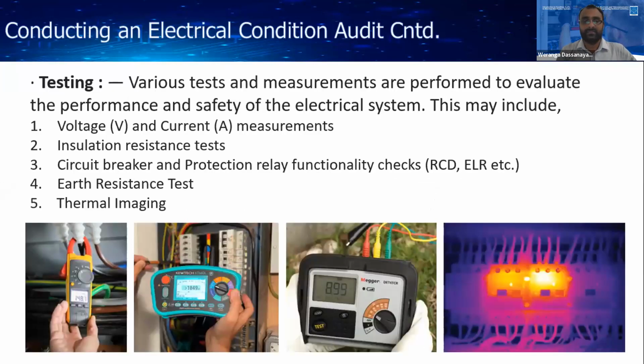Then the testing. There are several tests that can be done during a condition audit. First, you can take voltage and current measurements at several points: at MDB level, SDB level, power distribution board level and equipment level. The requirement is that you must have the required voltage level at every final point. That means if you check at a socket outlet, you must have the minimum voltage specified in the standard at that point. Otherwise, that system is not in good condition.